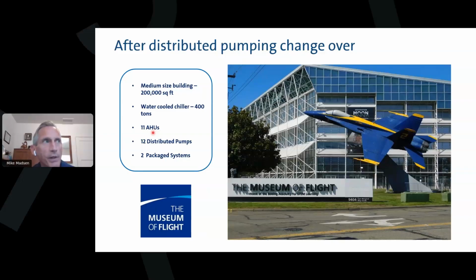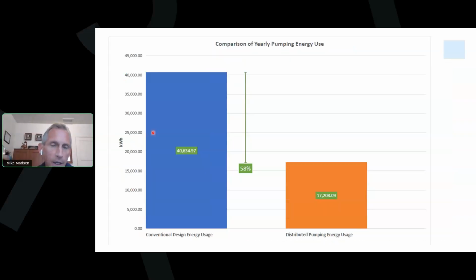And we have software. So one of the things we can offer you, if you're doing a building retrofit, or if you're an engineer that wants to present a traditional variable primary to distributed pumping, we can look at your existing system and we can estimate the energy savings. So we'll do a real nice energy report, and you can use that with your owners to say, here's how much we think you're going to save with distributed pumping. So here at the Museum of Flight, we estimated that they were going to save 58% on their pumping energy. And what they're actually seeing, when you get the video link, is that they're actually achieving 74% savings.